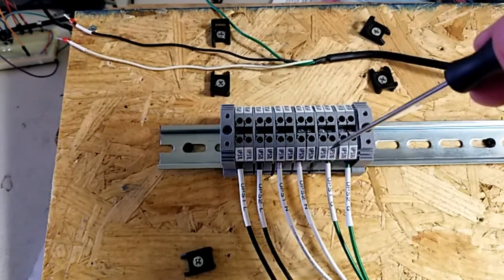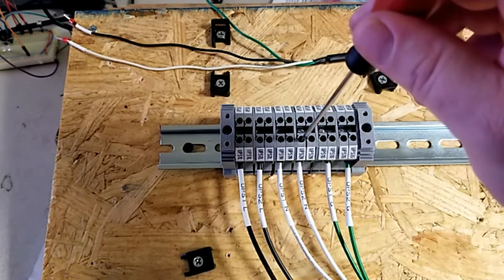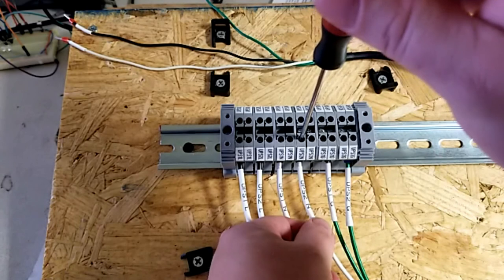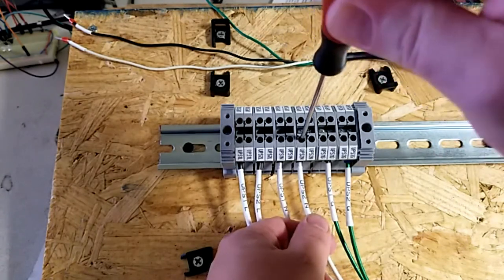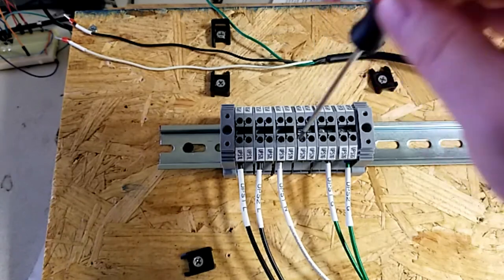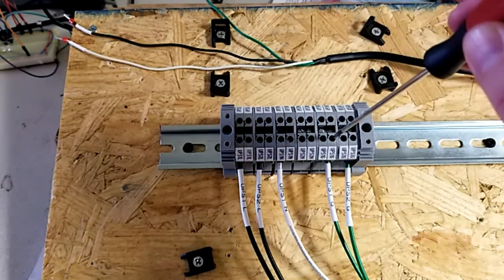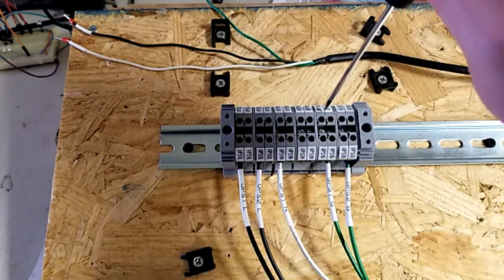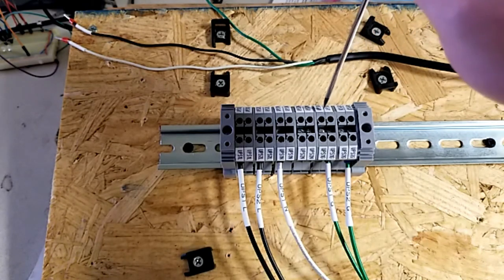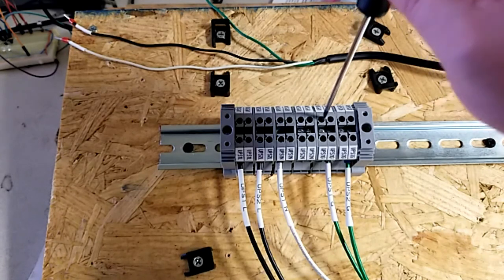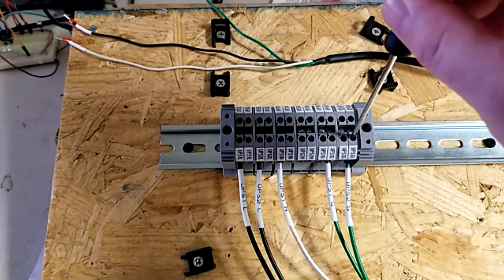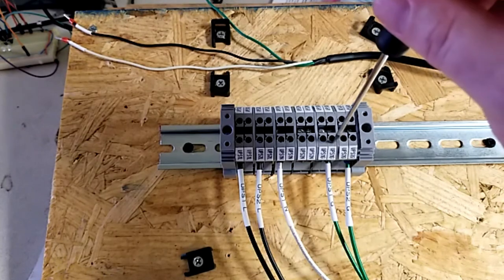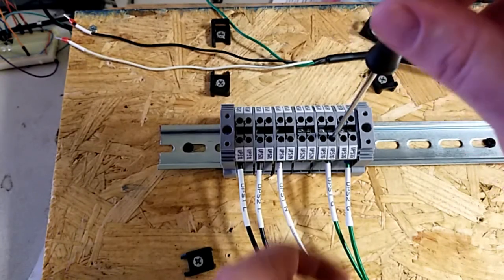From there, next we're going to remove the wires going to the bottom of this UPS2N terminals here. And then we're also going to be replacing these four ground terminals here. So any other ground wires, all your ground wires are going to be green, all the rest of the wires going into any of these four ground terminals, you can remove, you can temporarily remove, and we'll replace these terminals with grounding blocks.